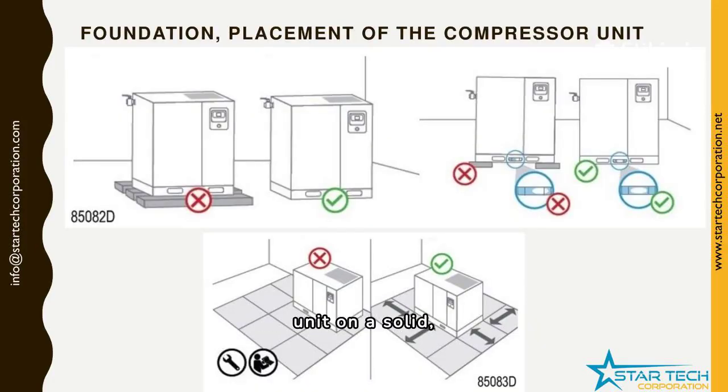Install the compressor unit on a solid, level floor, suitable for the compressor mass. It is not allowed to place any extra damping material between the floor and the base frame, so the frame is not supported on the complete surface.